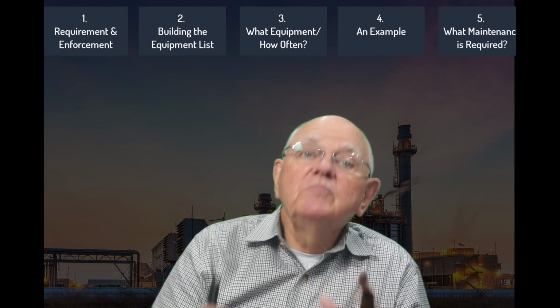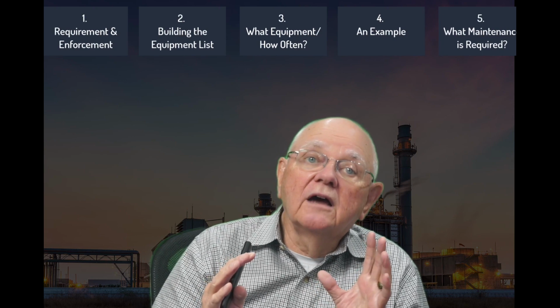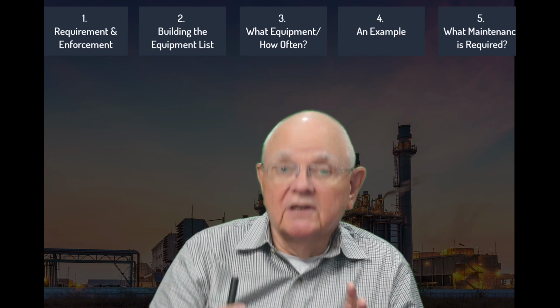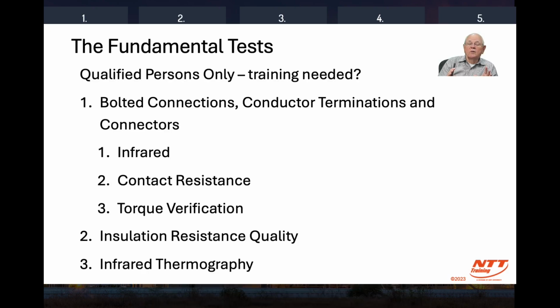Now, 70B identifies really three fundamental tests that we should always perform. First off, qualified persons, right? Qualified persons, meaning people have to be trained and knowledgeable in the construction and operation of that equipment if they're going to do maintenance. And so what are these three areas that we must do maintenance on? We have to do maintenance on bolted connections, our terminations and connectors inside of that transformer. We have to do insulation resistance testing on the windings in that transformer.